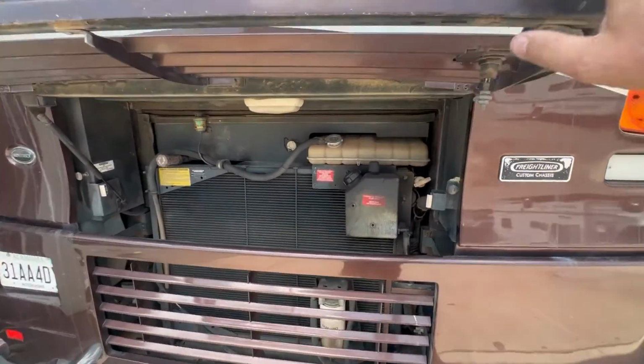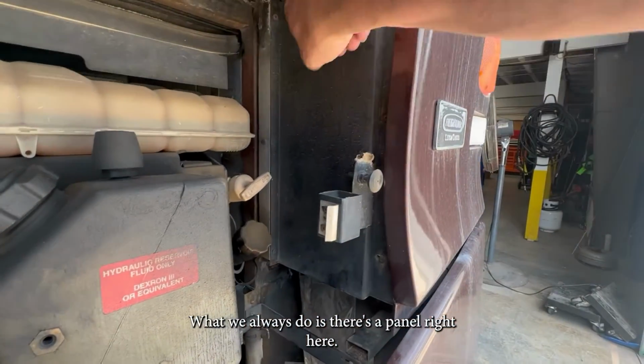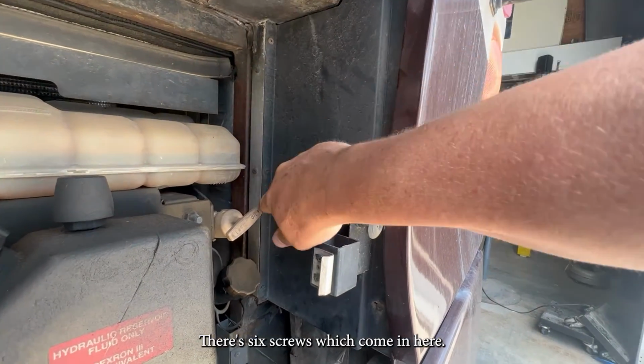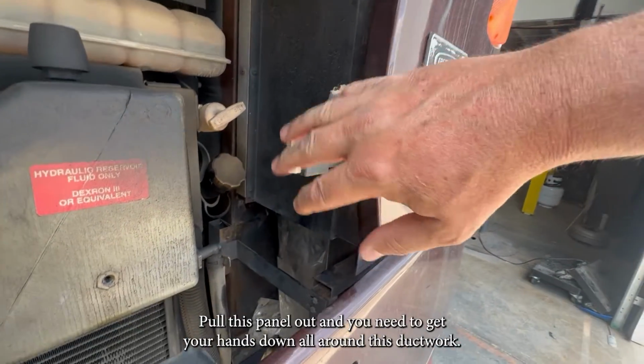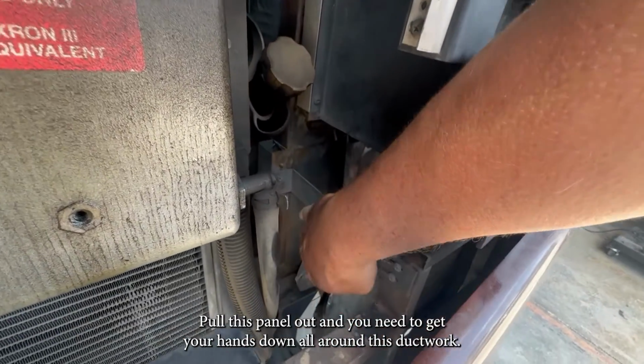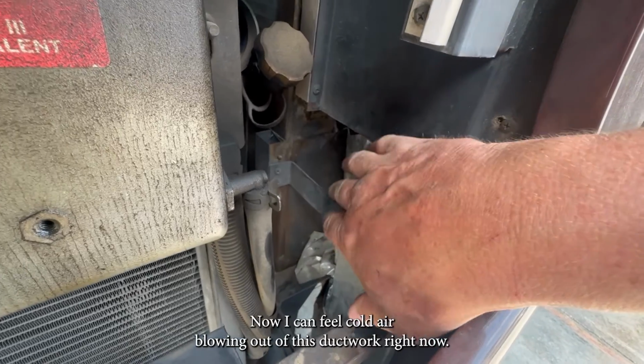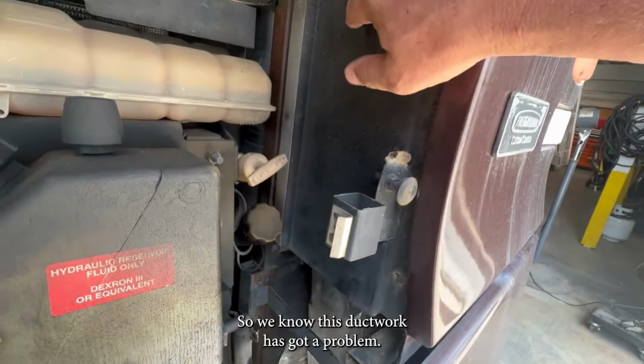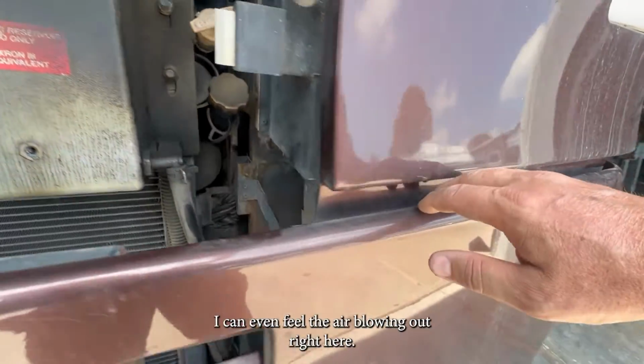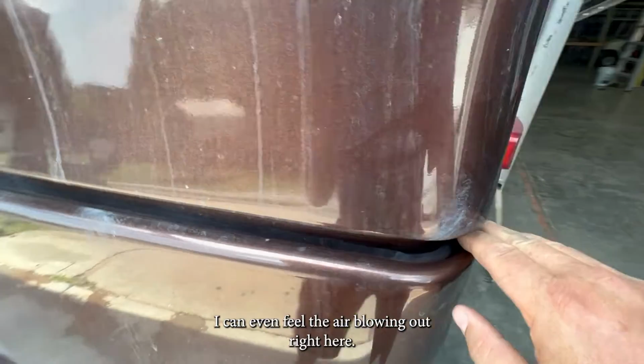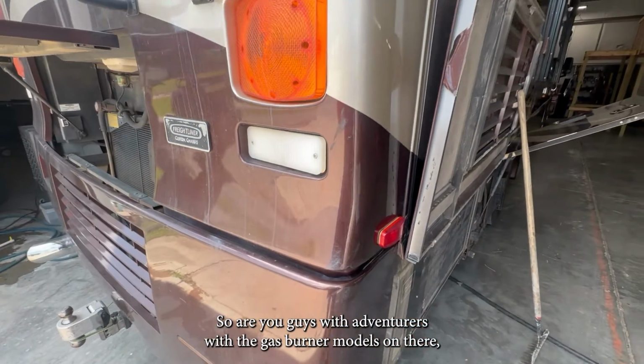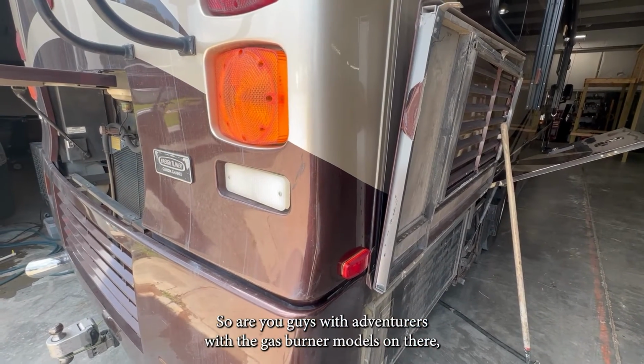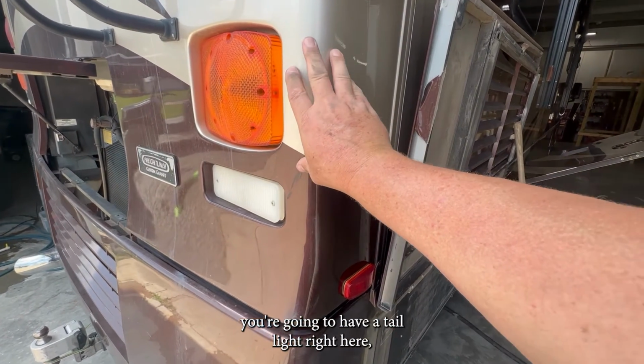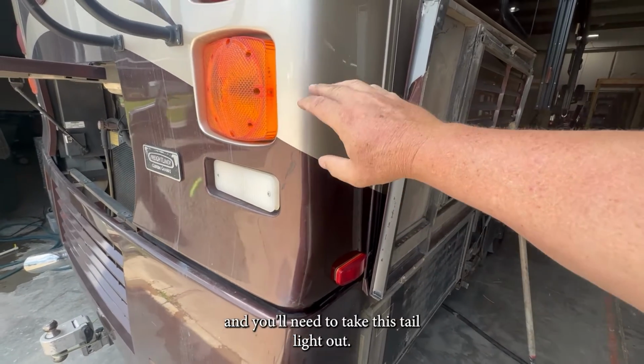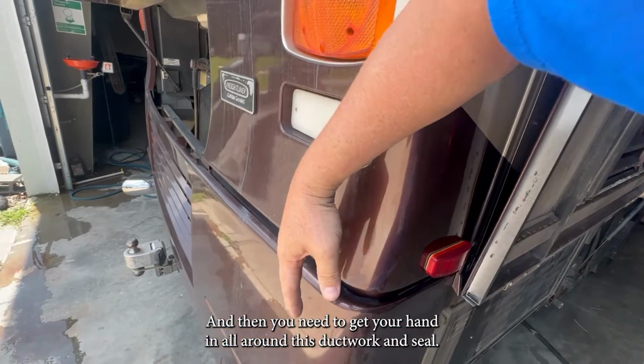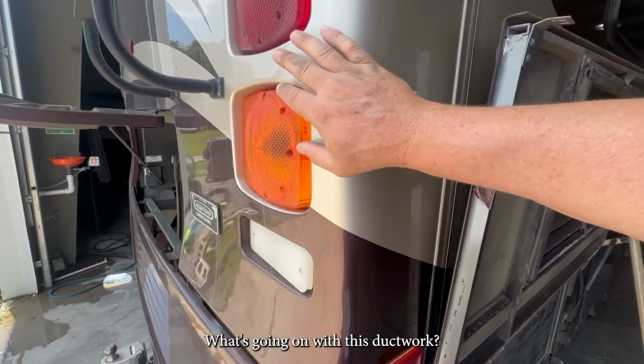Now, on a diesel pusher, what we always do is there's a panel right here. There are 6 screws that you come in here and pull this panel out, and you need to get your hands down all around this ductwork. Now, I can feel cold air blowing out of this ductwork right now, so we know this ductwork has got a problem. I can even feel air blowing out right here. So for you guys with Adventurers, with the gas burner models, you're going to have a tail light right here, and you'll need to take this tail light out, and then you need to get your hand in all around this ductwork and feel what's going on with it.